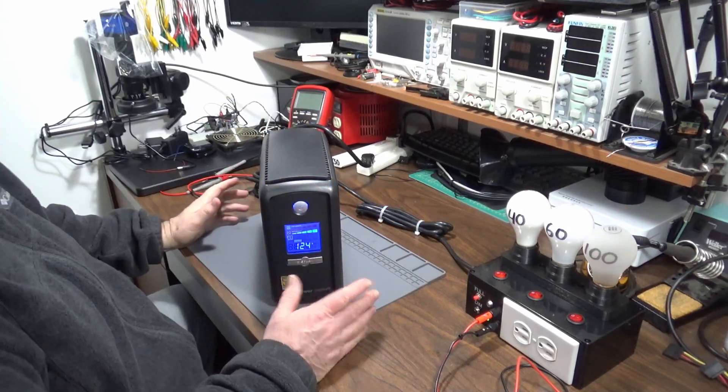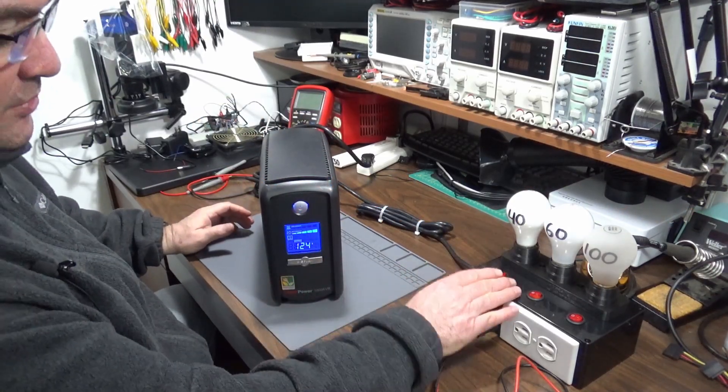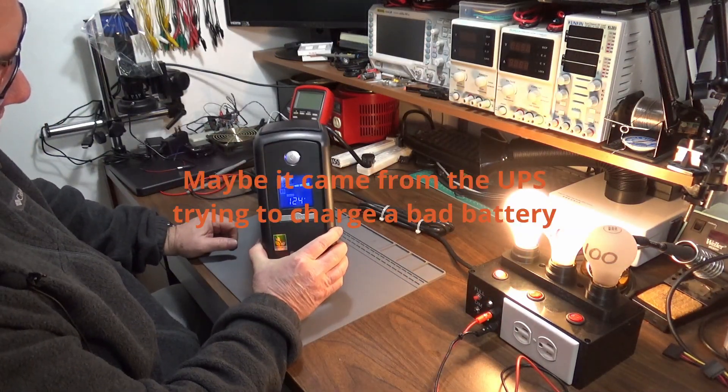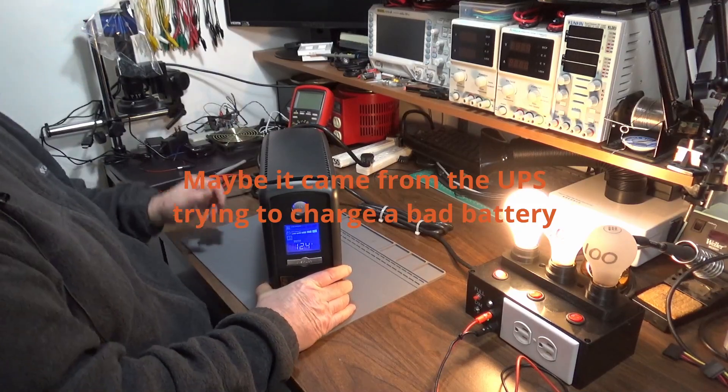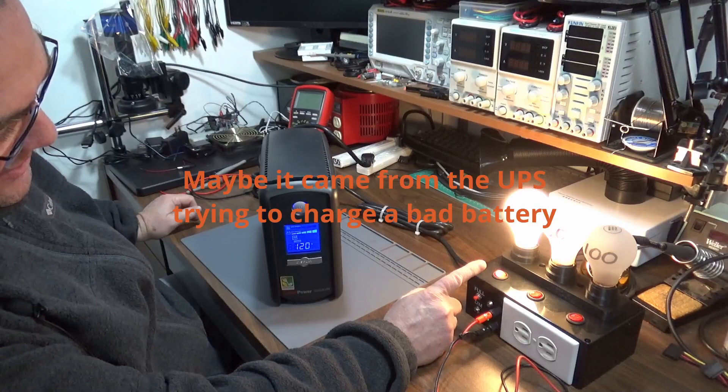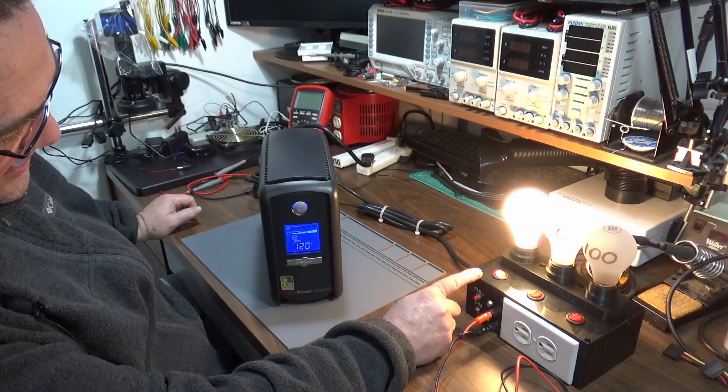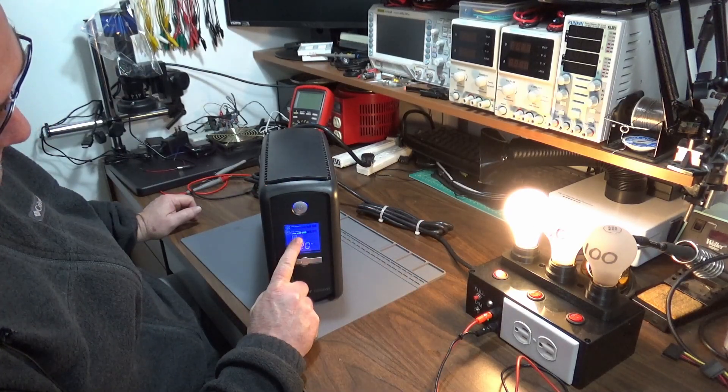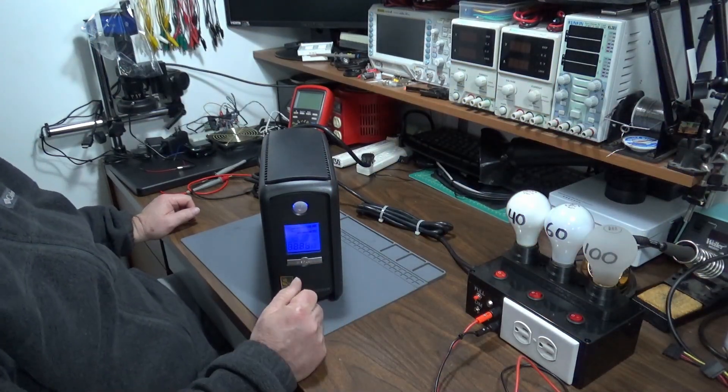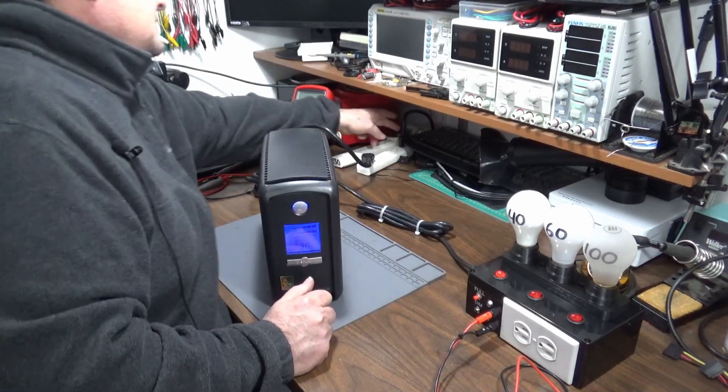So what I'm going to do on the bench is simulate a very light load, a 40 watt light bulb. Battery power shows full. Shut off the power. It maintains it. 40 watt load. Already beeping. Battery's gone to half. Battery's empty. And it shuts off. So that is a bad battery or signs of a bad battery.